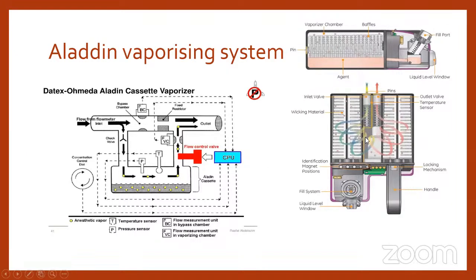This is the schematic diagram, where there are multiple wicks of metal wicking material to increase the surface area of contact. It has a rotator knob, a liquid level indicator, a filling system, a handle and a locking system. It also has an identification magnet position, which is different for each vaporizer. Isoflurane has a separate pin system, sevoflurane has a separate pin system, desflurane has its own pin system, and halothane too. Likewise, every anesthetic agent has a separate pin system for extra safety.